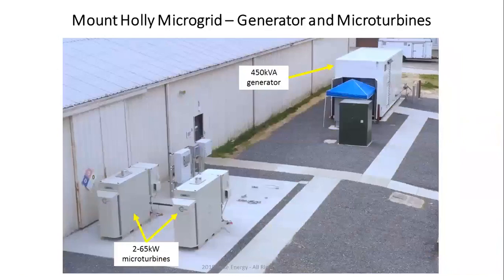And then the latest two additions, you can see a 450 kVA generator. We were currently last week doing the commissioning, so this is during the commissioning. And we also have two 65 kW turbines over here. So essentially, the only thing that's missing over here is the 480 volt switchgear that's coming probably within the next 2 to 3 weeks, and we will be commissioning these two 65 kW turbines.